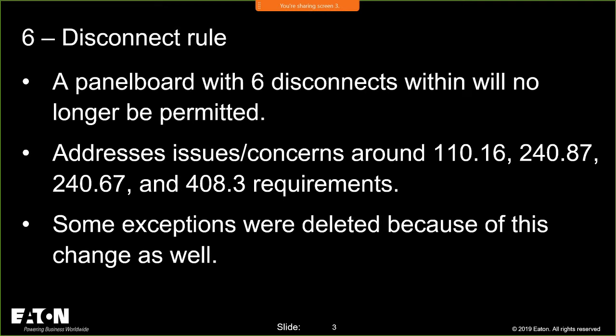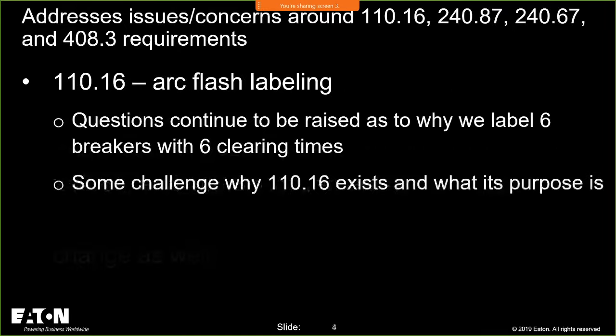They're having a lot of issues there. But right now, because of the words in the code with compartmentalization, there's nothing on the market that will meet that from a meter center perspective. Meter stacks, different story. Meter centers, so you'll probably see mains in front of meter centers to meet that code requirement. Again, we're addressing the issues of 240.67 and 408.3 and how that influenced these changes and the deletion of that exception. We talked about the fact that 110.16 has all of these labeling requirements. If I had 6 disconnects, I'd have to have 6 labels of available fault current, 6 sets of clearing time, which absolutely does not help anybody other than the label manufacturers. So these changes will clear that issue up in 110.16 as well.